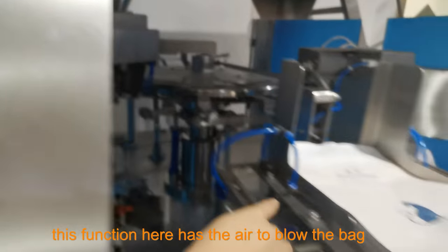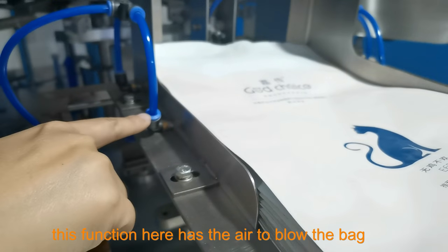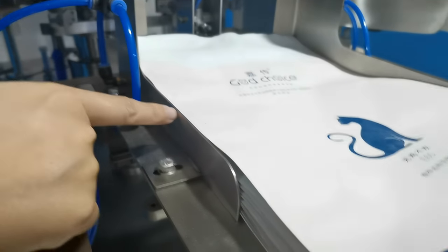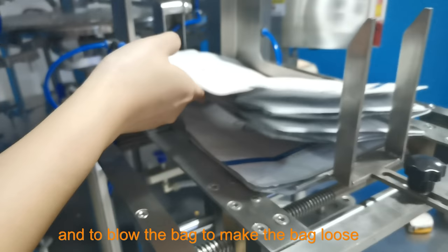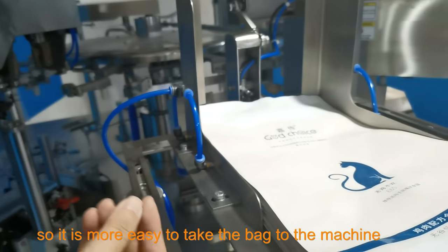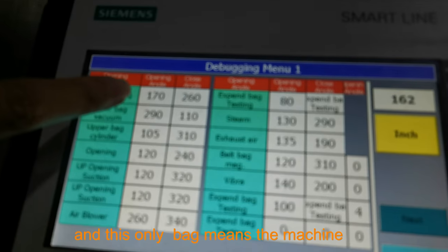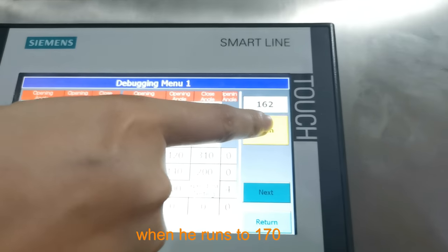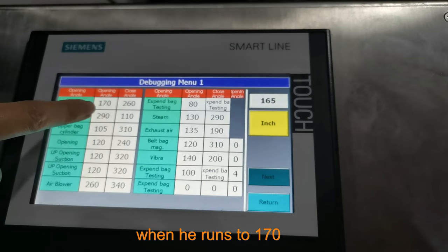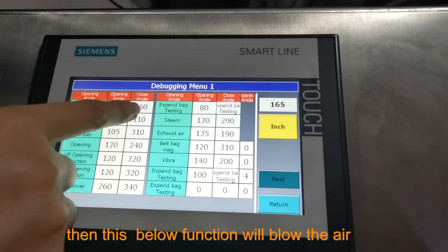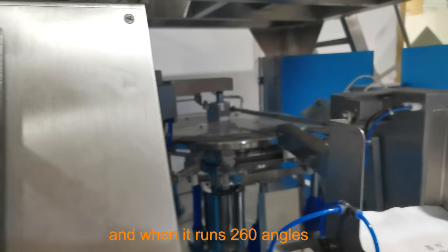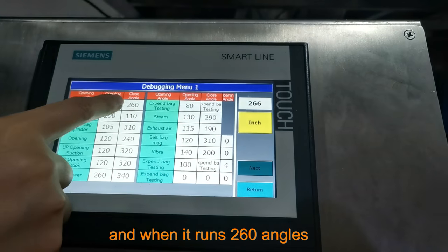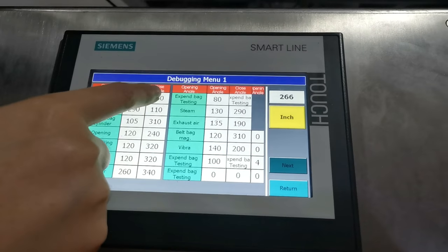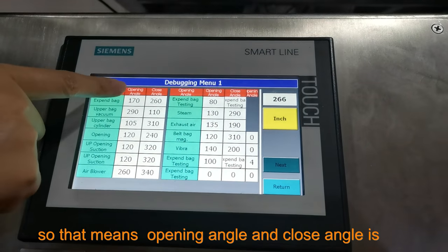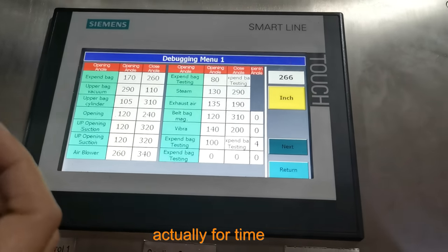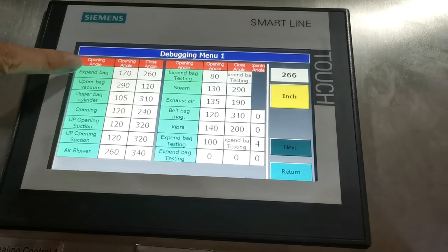For example, expand bag means this function has air to blow the bag and make the bag loose, so it's easier to take the bag to the machine. And this opening bag means when the machine runs to 170, then this blow function will blow the air. And when it runs to 260 angle, then this function will stop. So opening angle and close angle is actually for the time when the action starts and stops.